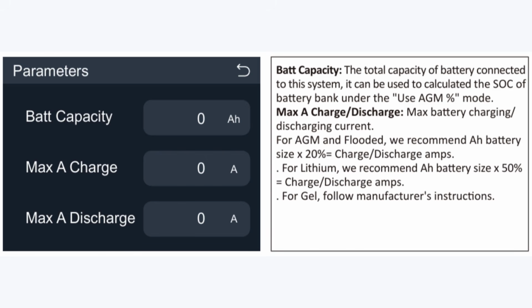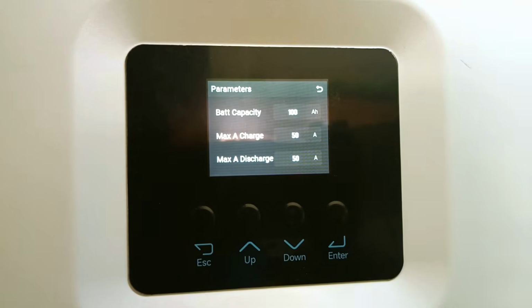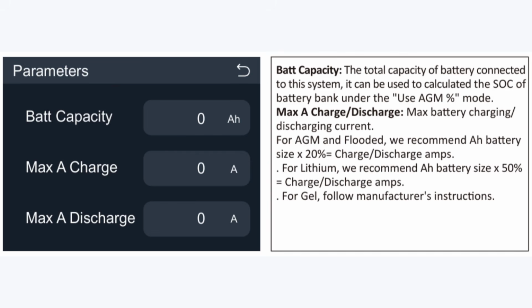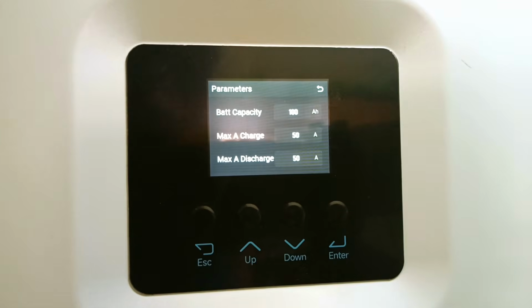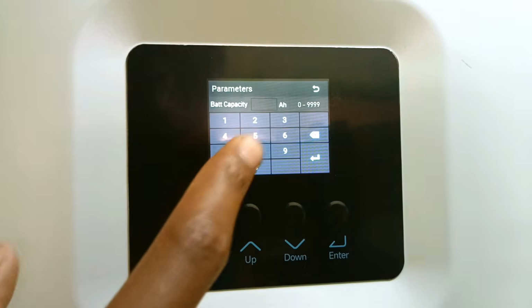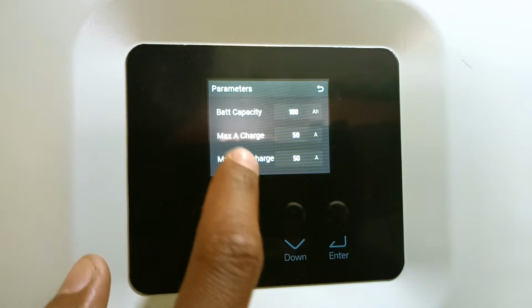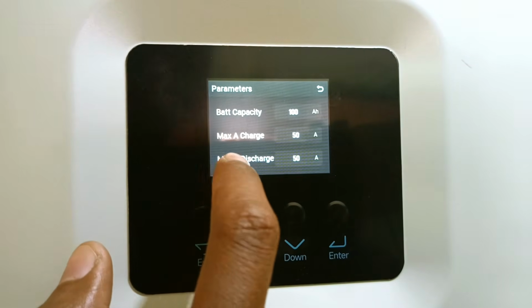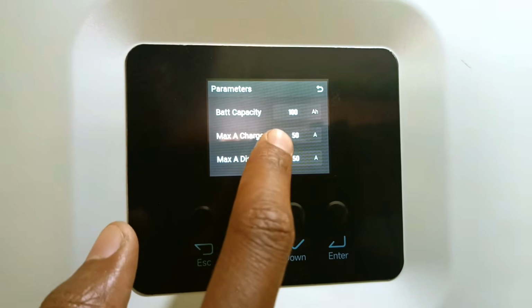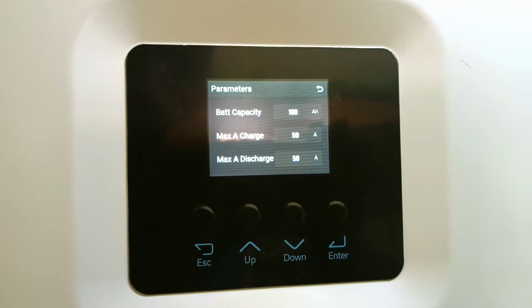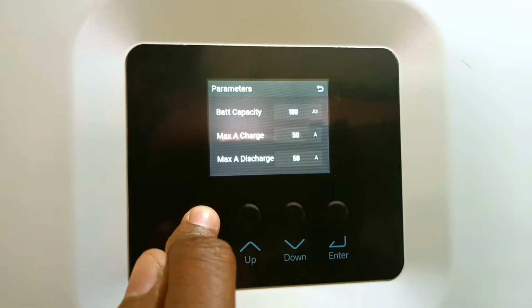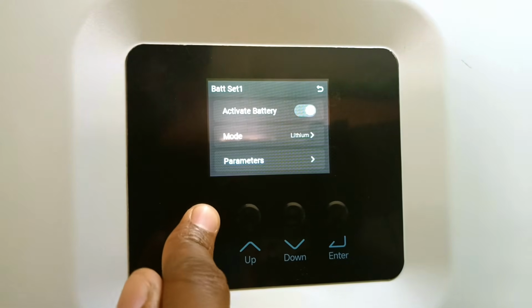Maximum battery charging and discharging current. For AGM and flooded, we recommend battery size times 20% is the charge or discharge amps. For lithium, we recommend battery size times 50% is the charge and discharge amps. For gel, follow manufacturer's instructions. Now, as you can see, my battery is 100, I had to input that manually. And the maximum charging and discharging current is 50% of the battery capacity, which is 50 amperes. And that's what I have set. And that's all to do with the battery settings.